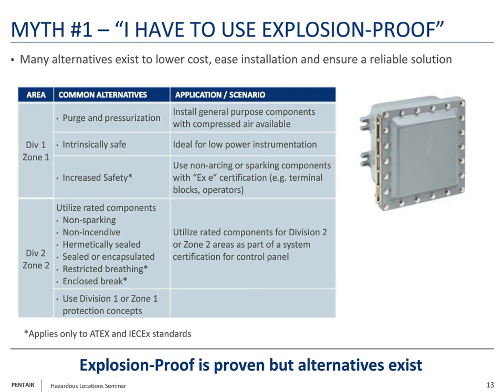Intrinsically safe is a great alternative if you're doing low power, instrumentation type applications. Increased safety is really only applicable to ATEX and IECEx, but it's great if you can use non-arcing and non-sparking components like terminal blocks or operators that are certified. So those are alternatives that can be lower cost or a better solution for various applications.